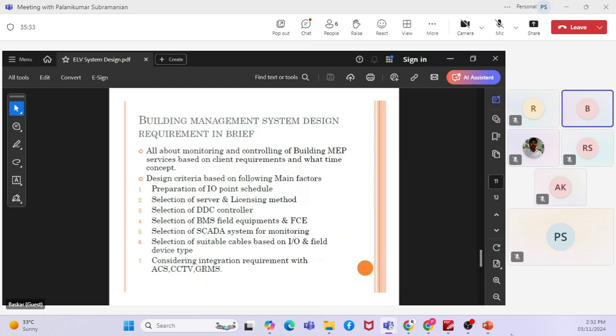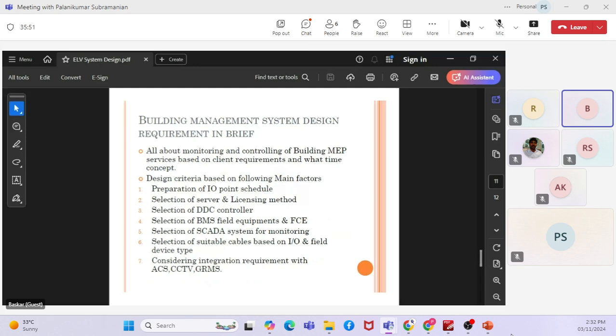Now the other system, in brief, the building management system. You are aware of the building management system, I believe. It's monitoring and controlling of the MEP systems. That is the BMS, building management system. It controls and monitors all the connected MEP equipment. Again, we need to choose the monitoring and control based on the client and consultant requirement, not to overcost or undercost. So how to choose this BMS system, the following criteria are mentioned here.